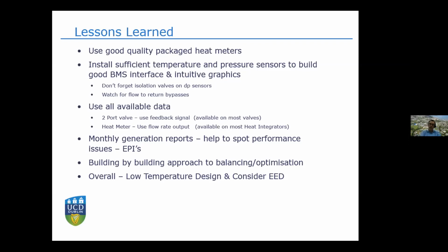Then a building-by-building approach to balancing. This will be key for us moving forward - the delta T on the system, especially now with heat pumps, taking a balance from the secondary side of a building up to our heat exchanger, a bottom-up approach, building by building, starting at the biggest building and working your way up on a continuous cycle. Maybe every couple of years you revisit them, because people go in, modify things, respond to complaints or issues, and before you know it commissioning valves have been opened or adjusted.